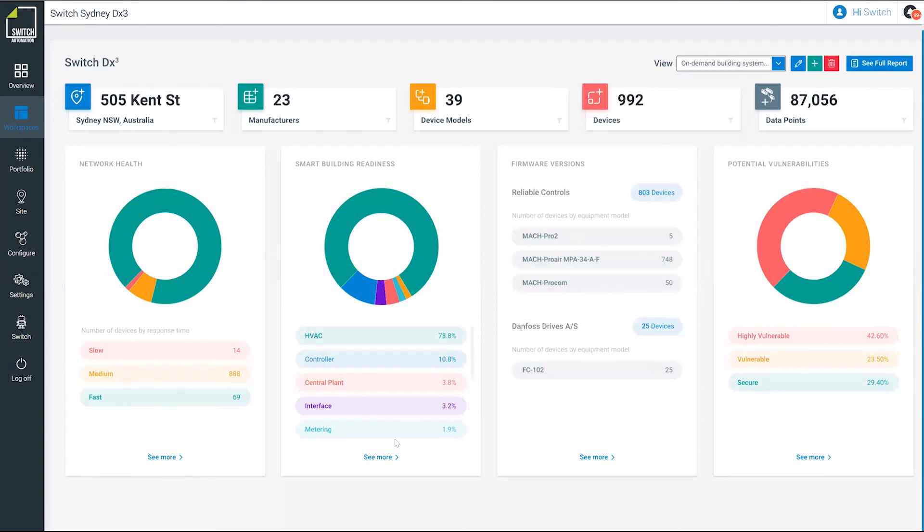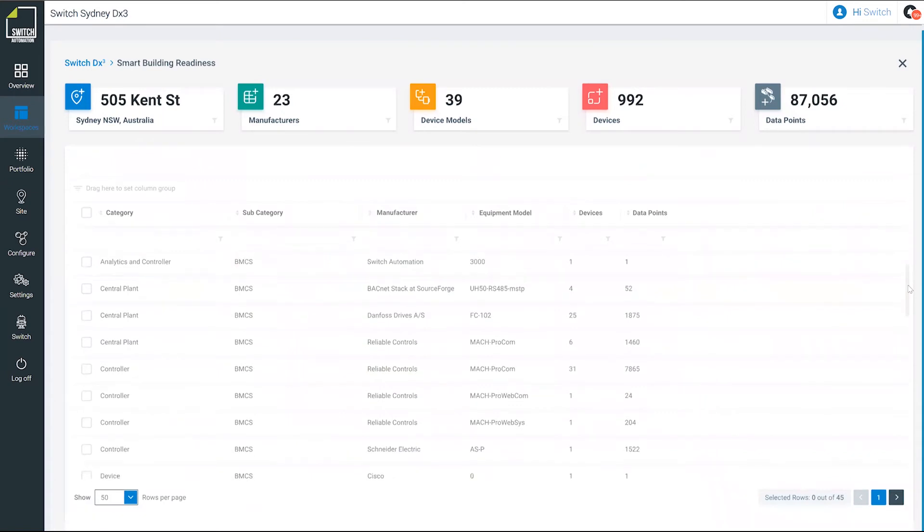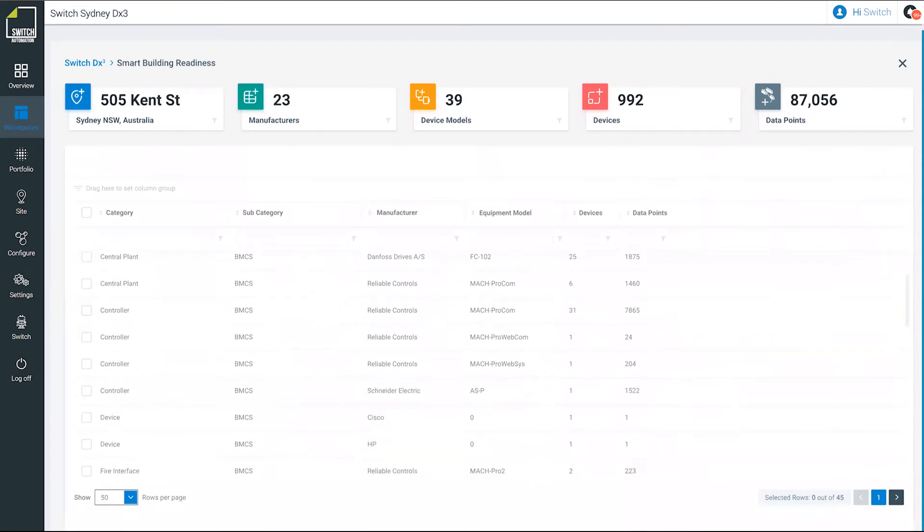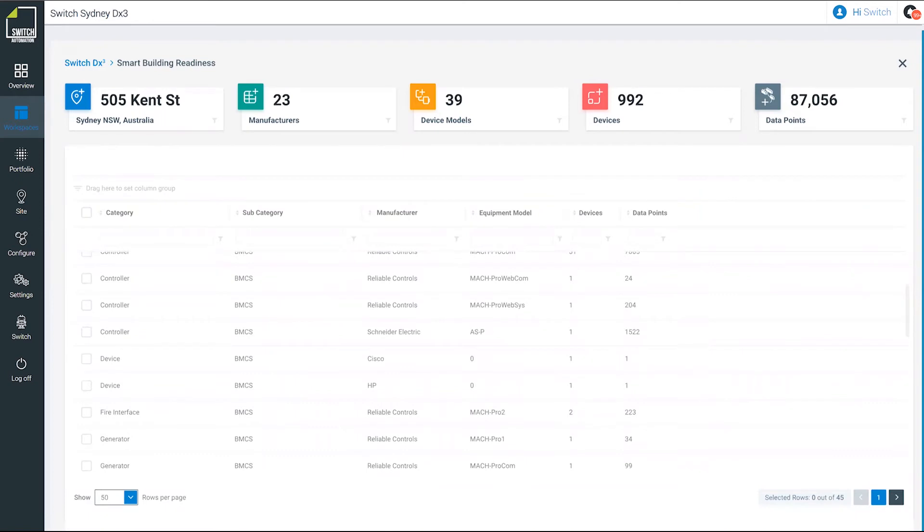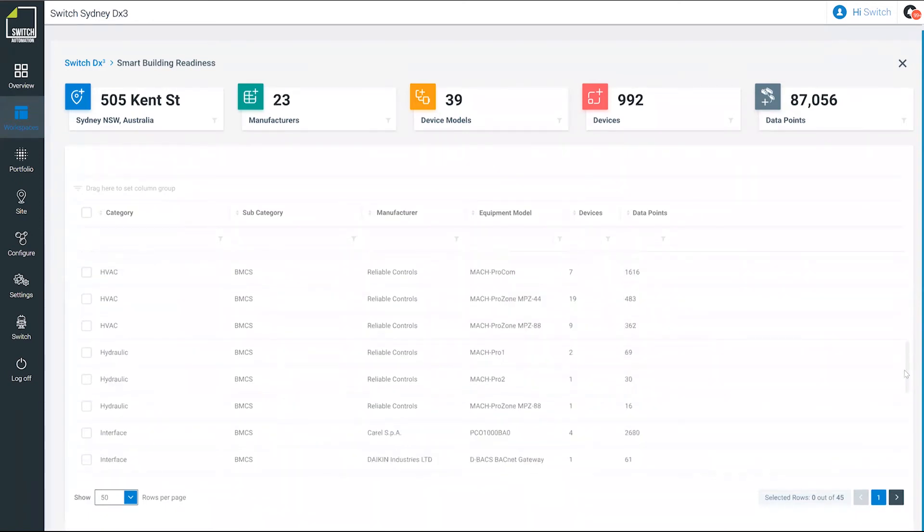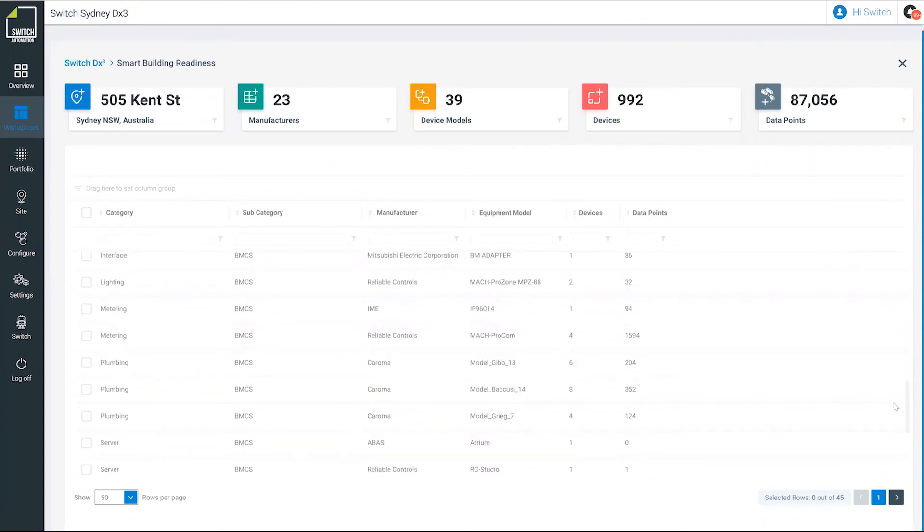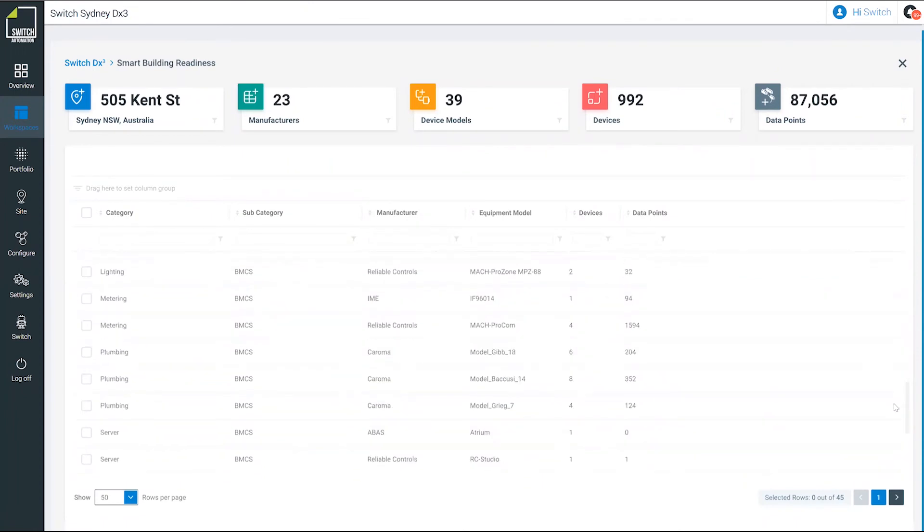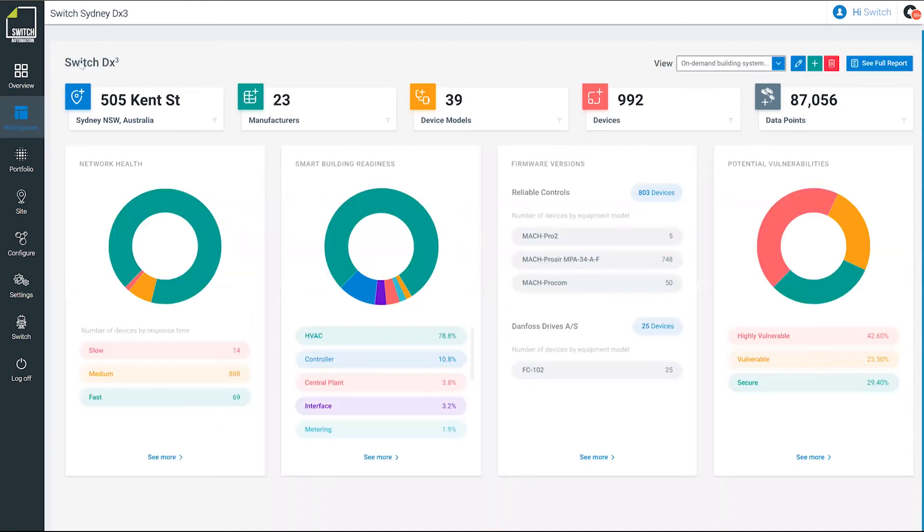The next one is really all about discovering the smart building readiness. What systems have we found in the device discovery? We've found some central plant equipment here. You can see we've found some Danfoss drives, more reliable controllers, some Schneider electric metering here, Cisco switches. There's even, I scanned the list earlier, there's some Caroma smart tapware, there's some Daikin. It's quite a comprehensive list. Yeah, there's the Caroma smart bathroom ware in there. There's a VMware machine. You can see here we've done a full, essentially IP discovery. But we've also identified integration ports to BACnet and Modbus through discovery of the manufacturers like Schneider and obviously reliable controls.